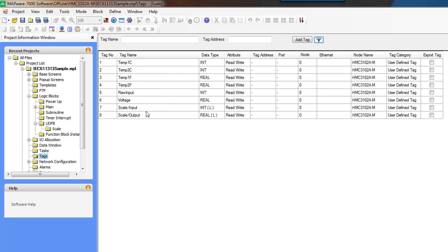So these are the tags that we created from the tag database. These are all global scoped. And then these are the tags that are local scoped to our UDFB scale. And the nomenclature goes scale slash input, scale slash output. That indicates that these tags are local to the scale function block.